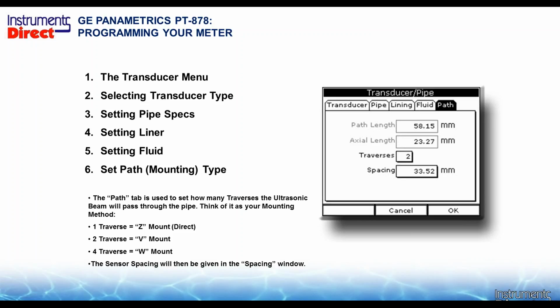Now, here we need to select the method of the transducer. Are both sensors on the same side of the pipe or one on each side of the pipe there? So as I said, the V-mount will be done most of the time. Generically speaking, we do that method from 2 inches to 24 inches, and then larger than 24 inches is a candidate to do the Z-mount. Not always the rule, depends on the pipe conditions and the pipe quality there. I've done some V-mounts on 90-inch pipes before. But generically speaking, when you get an older, crusty old pipe there, you're going to lose your sound. The Z method is a much more powerful transmit signal because it's only going across the pipe and back. It's not bouncing off a wall and ricocheting. When it does that, it probably loses half of its intensity. So keep that in mind for your applications.